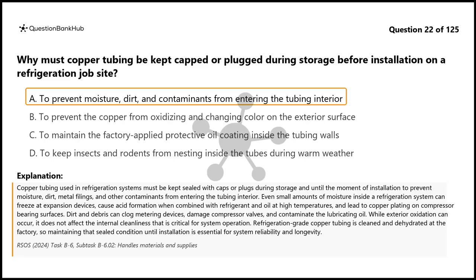While exterior oxidation can occur, it does not affect the internal cleanliness that is critical for system operation. Refrigeration-grade copper tubing is cleaned and dehydrated at the factory, so maintaining that sealed condition until installation is essential for system reliability and longevity.